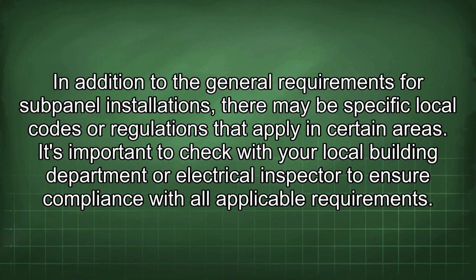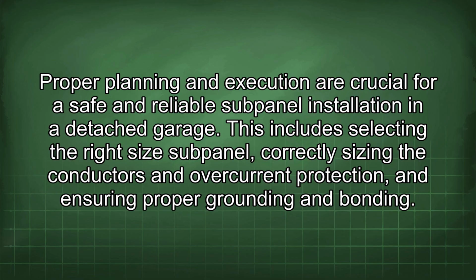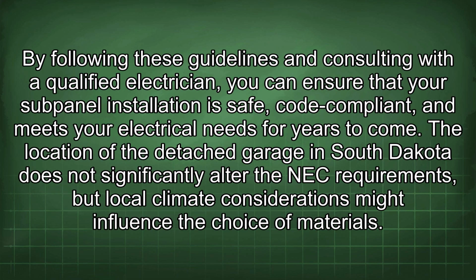The disconnect should also be clearly labeled to indicate that it controls the power to the subpanel. In addition to the general requirements for subpanel installations, there may be specific local codes or regulations that apply in certain areas. It's important to check with your local building department or electrical inspector to ensure compliance with all applicable requirements. Proper planning and execution are crucial for a safe and reliable subpanel installation in a detached garage. This includes selecting the right size subpanel, correctly sizing the conductors and overcurrent protection, and ensuring proper grounding and bonding. By following these guidelines and consulting with a qualified electrician, you can ensure that your subpanel installation is safe, code compliant, and meets your electrical needs for years to come.